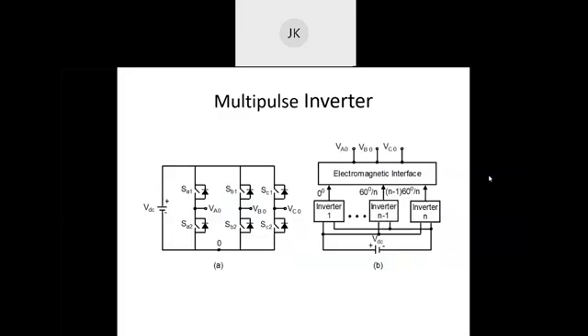So multipulse inverters I will not discuss in detail, just in 1 or 2 slides. Figure A shown on the left side is basically a 3-phase inverter producing 6 pulses. As the number of pulses increases, THD goes down. So to reduce THD, we combine or integrate basic single 6-pulse inverter units.